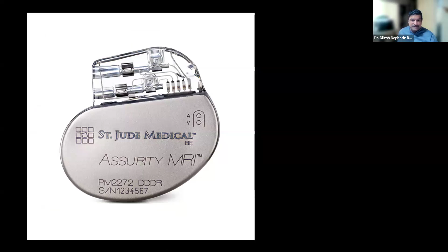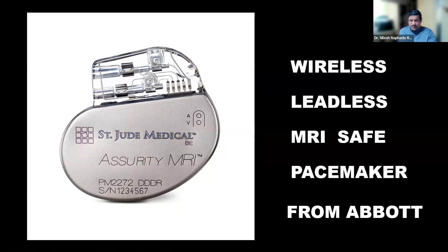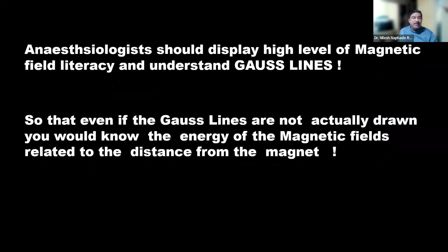This is a wireless, leadless, MRI safe pacemaker sold in India by Abbott. You can use this. An anesthesiologist also can require a pacemaker, and you will have to go into the MRI suite with this pacemaker. As you see, the pacemaker clearly mentions it is MRI safe. So if an anesthesiologist says that I thought there was no patient, so the machine must be off and the magnetic field of the MRI must be off, the anesthesiologist is ignorant about a magnetic field. I want to tell everybody, anesthesiologists should display a high level of magnetic field literacy and understand Gauss lines, so that even if the Gauss lines are not actually drawn in your MR room in your department, you would know the energy of the magnetic fields related to the distance from the magnet.